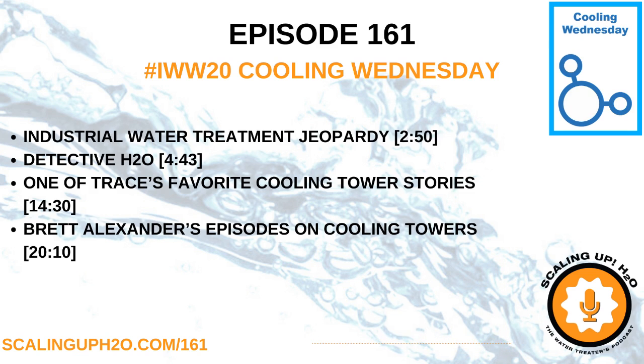Let me show you. The water detective led her back to the water testing station, poured the cooling tower water sample into a sample vial, and said, Now watch what happens when I place the free chlorine test reagent powder into the sample. It's just clear, Mr. Oxidane. That means no free chlorine.